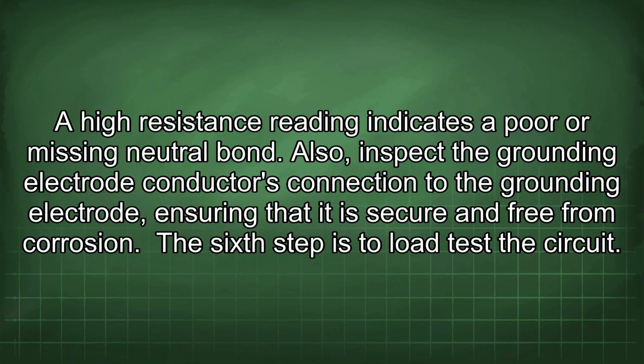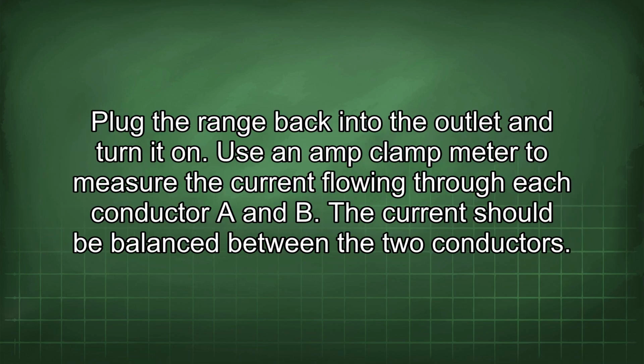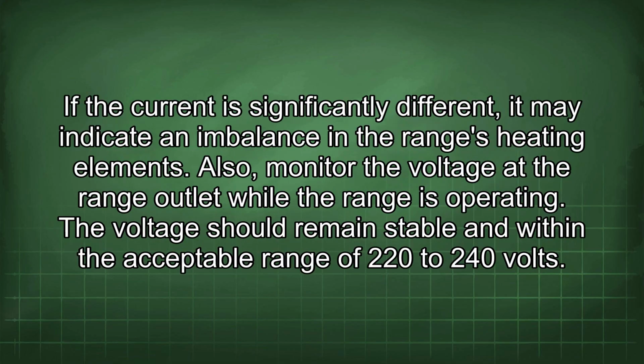The sixth step is to load test the circuit. Plug the range back into the outlet and turn it on. Use an amp clamp meter to measure the current flowing through each conductor A and B. The current should be balanced between the two conductors. If the current is significantly different, it may indicate an imbalance in the range's heating elements.